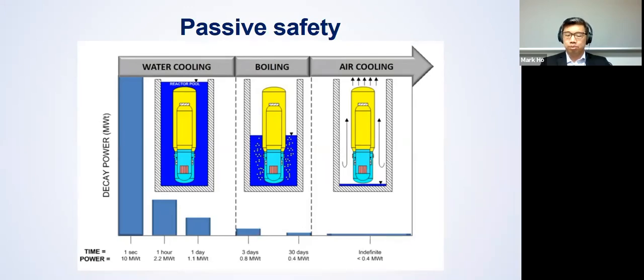And in this particular example for NuScale, there's enough water so that it could basically be what's known as walk-away safe, because after a long period of time, the decay heat reduces to such an extent that just natural circulation of air is enough to remove the decay heat after the reactor's been shut down. And of course, the reason for doing this is so that in case you have a station blackout event, as there was over in Fukushima, then you don't actually have to worry, because you've got all that cooling capacity there to remove that decay heat, and you won't have any meltdown.